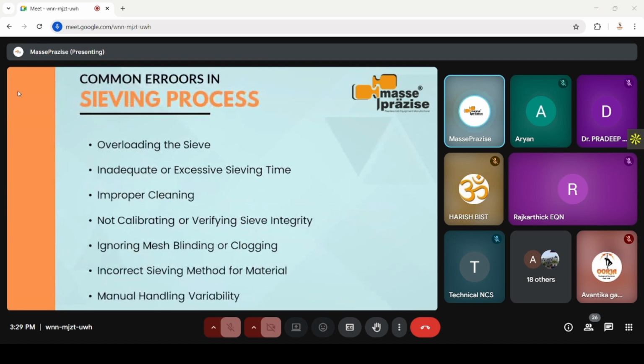Common errors in the sieving process: overloading the sieve. Loading too much material at once may lead to insufficient separation, damage to the mesh, and increased blinding. What amount of sample to be used can be taken from the industry standard or local standard, like in USP 786, it is recommended to use a maximum sample size of 100 gram. So depending on the size of the sieve, you may use from 15 gram to 100 gram sample, and over 100 gram is not recommended there.